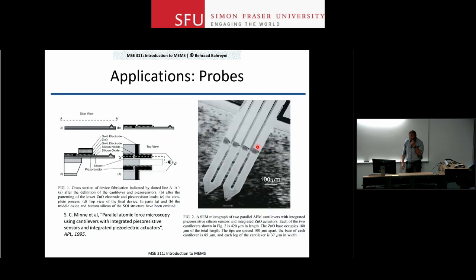And finally, here is a probe where you have a piezo layer here. This is an AFM probe. We talked about this early on in the course. The probe goes across the surface, and if you have roughness on the surface, it goes up and down in response to that roughness. What you need to do is to measure how far this probe has gone up and down, and then by rastering the surface, you can basically map the roughnesses on that surface. Normally, this is done with an optical setup. You shine a beam of laser to the back of this probe, and you look at the movements of that beam of light, or that spot of light on the sensor.